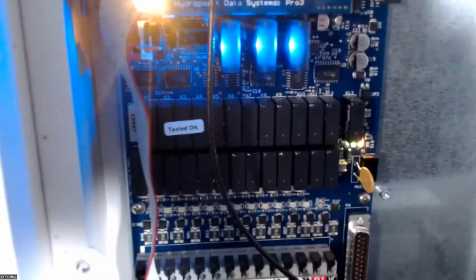Another thing I use the LED lights for is finding bad commons. If you have a bad common wire or connection, power goes out at the station level, but if it doesn't have a path to return on the common wire because it's broken, it'll jump across solenoids and reverse-light some of the other LEDs. You'll see like 4 or 5 LEDs come on at once, like a Christmas tree, and that helps me troubleshoot too.